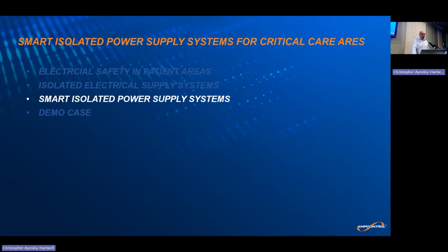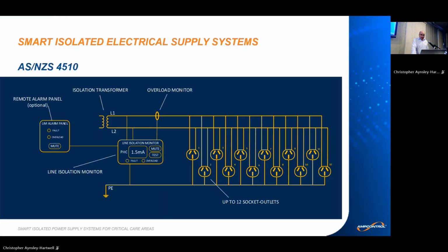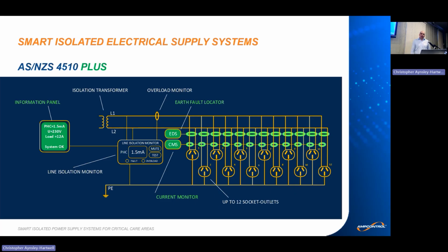So I think you can agree that we cannot call this system intelligent, but luckily there is technology available that can make this system smart. And let me show you how a smart isolated power supply system works. In order to comply with AS 4510, a smart isolated electrical supply system also provides line isolation monitoring and overload monitoring, but it also provides current monitoring of each individual circuit and automated earth fault location. And instead of an optional alarm panel, a smart isolated electrical supply system includes an information panel.